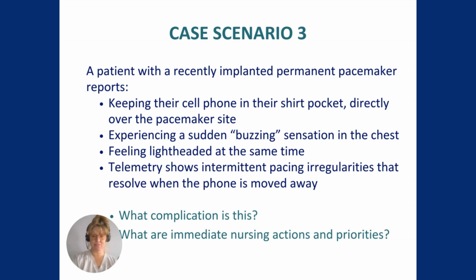Nursing priorities. First, remove the source of EMI. Ensure the phone is kept at least 6 inches away, ideally carried in a pants pocket or a bag, never over the pacemaker site. Assess and monitor: check vital signs and symptoms, and confirm the rhythm normalizes upon removing the source. We're going to review the telemetry, looking for pacing inhibition, noise, artifact, or mistimed spikes. We're going to be vigilant with our monitoring.